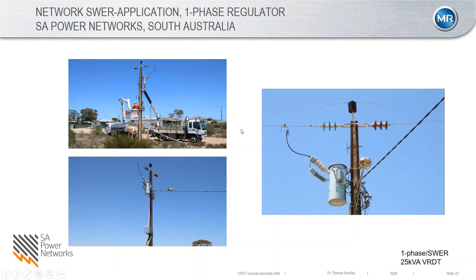So that's the single phase unit installed, I think south of Adelaide there. Just a small pole tranny, and the network operator SA Power Networks has also allowed me to share some results. So here you can see some results prior to the installation of the transformer and also after the installation. Just be aware the upper picture is just 10-minute aggregated readings, where the one below, after the installation, is 10-second aggregated readings. So it looks a little bit unsmooth there, but of course much higher resolution.